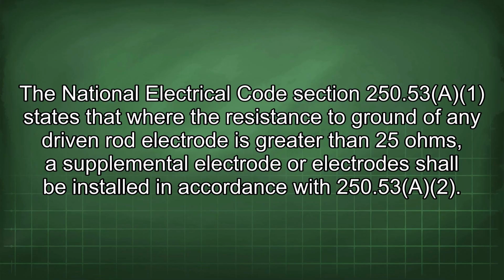The National Electrical Code Section 250.53 states that where the resistance to ground of any driven rod electrode is greater than 25 ohms, a supplemental electrode or electrodes shall be installed in accordance with 250.53 (A)(2).